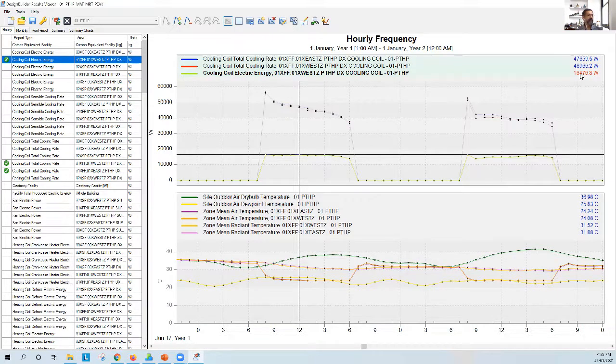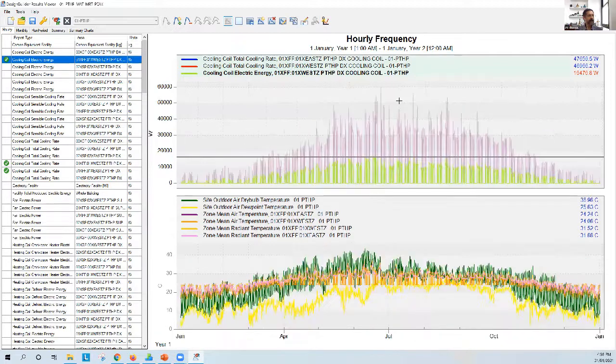And the COP varies depending on the outside air temperature, what's the load, what's the condenser air temperature, and a bunch of other things. So it's quite a complex relationship to do that. So that'll then start to give you all the electrical energies that you are looking for.